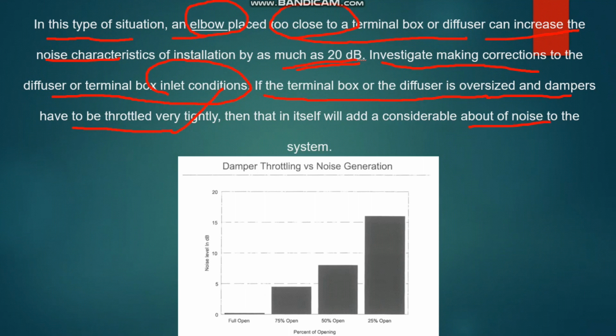For example, you can see here in the X direction I have given the percentage of opening of the damper, and in the Y direction I have given the noise level in decibels. If the damper throttling is 25% open, you can see the noise level is more than 15 decibels, around 16 decibels. If it is 50% open, then the noise level will reach around 8 decibels, and if it is 75% open, it will be around 4 decibels. If it is fully open, then the noise will be avoided.